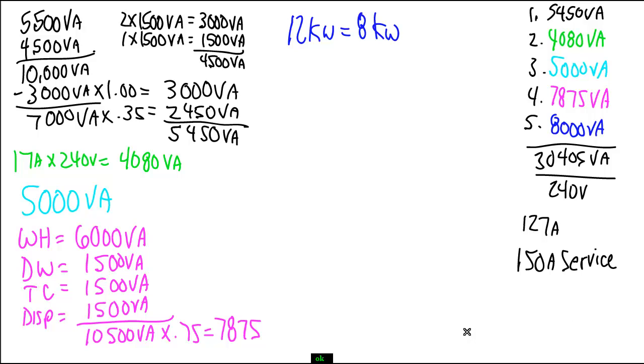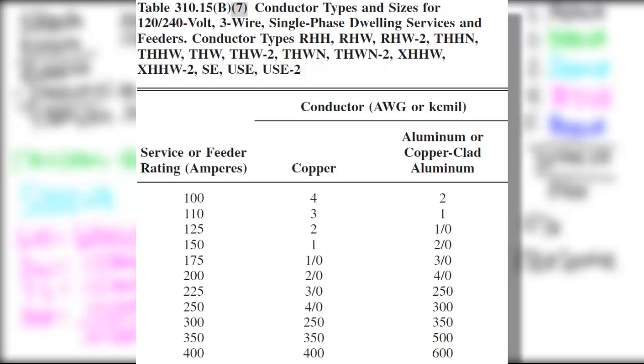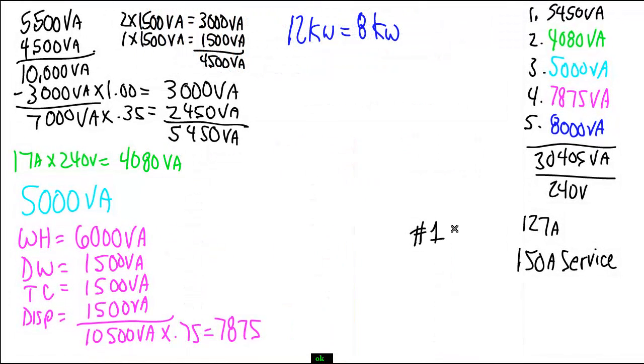Well, what size of service feeder would I need to be using? What you need to do to find that out, because we're in a dwelling unit, and these rules only apply for dwelling units, you can use table 310.15B7, which is only for 120, 240 volt, three wire, single phase dwelling services. When I go down to the column that says 150 amps, and I go over to the column for copper, I need a number one copper conductor for this service.